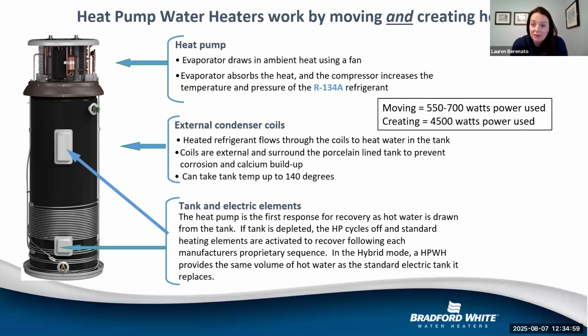Really good question. The challenge with Legionella is it's constantly breeding. It obviously gets instantly killed at 158 degrees Fahrenheit or above, but once you are below that temperature threshold, it's going to be sitting there growing in your tank with some type of bacteria growth. I think the most important thing to remember, so first, vacation mode, is that on all units? I don't know. I know for residential it is, and it drops it down to around 90 degrees Fahrenheit. I'm not an expert in all manufacturers' products. I would assume it is, just because typically with these types of things, if one person has it, then all of a sudden everyone has it.